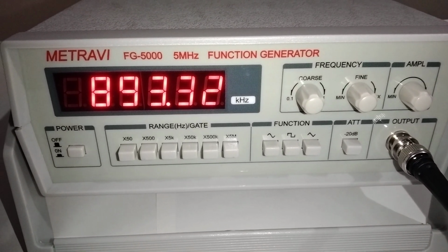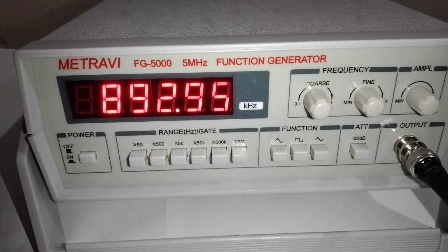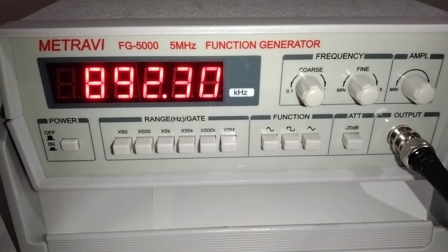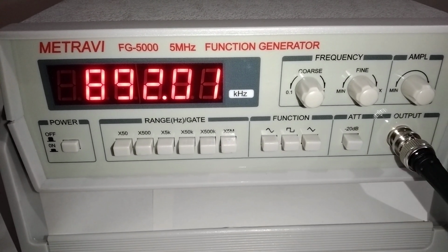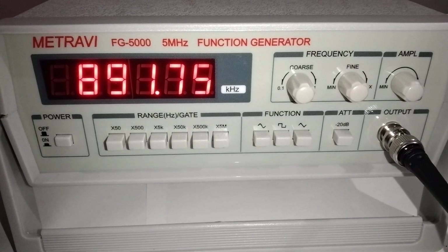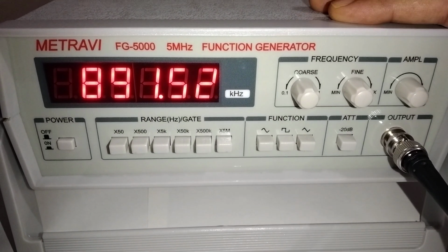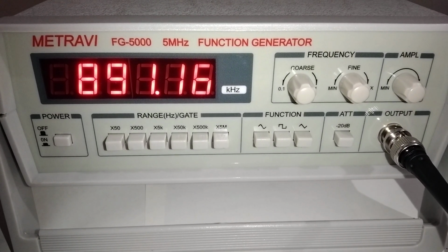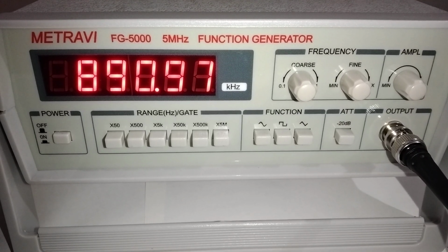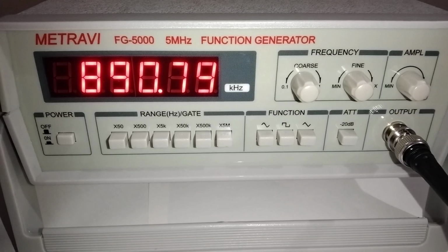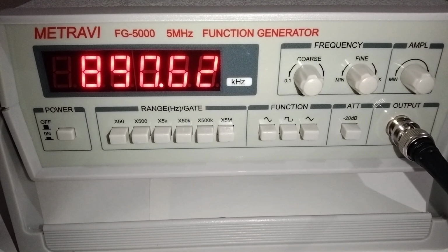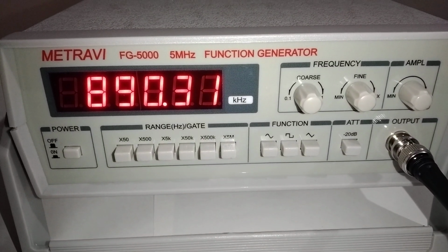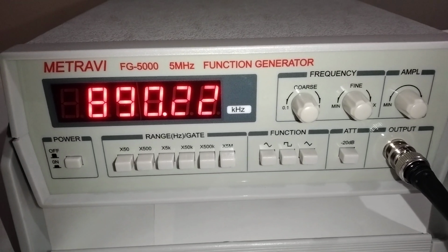Now here as it is written that is a 5 megahertz, that means it can generate the waveform, or it can output a waveform up to 5 megahertz frequency. So basically, as we are aware that the name of the function generator means it is used to generate a different waveform, and which can be given as a test input to any of the circuitry or for any of the application. Now here the minimum frequency is 5 hertz and maximum is 5 megahertz.